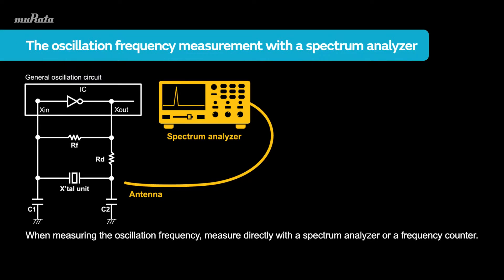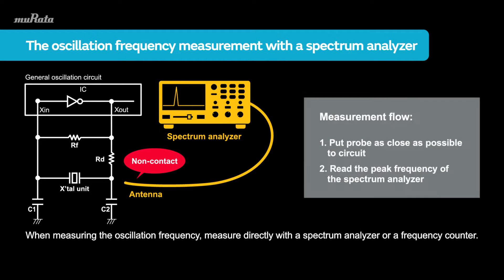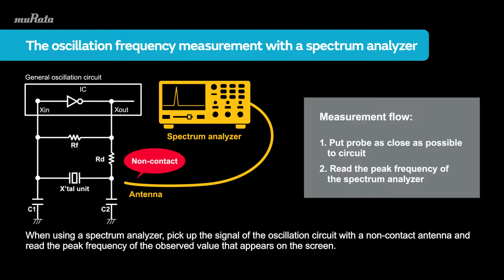When measuring the oscillation frequency, measure directly with a spectrum analyzer or a frequency counter. When using a spectrum analyzer, pick up the signal of the oscillation circuit with a non-contact antenna and read the peak frequency of the observed value that appears on the screen.